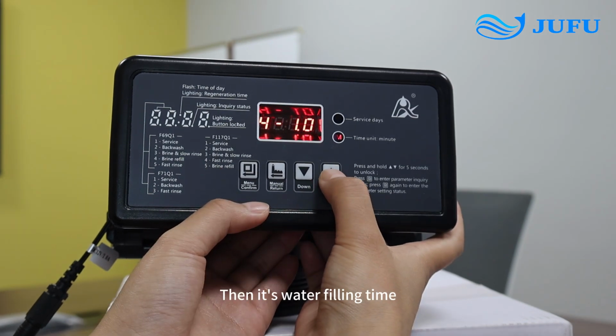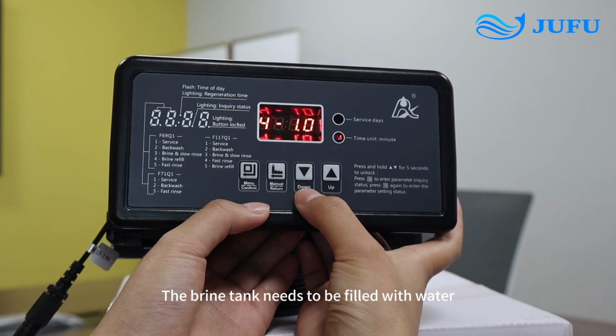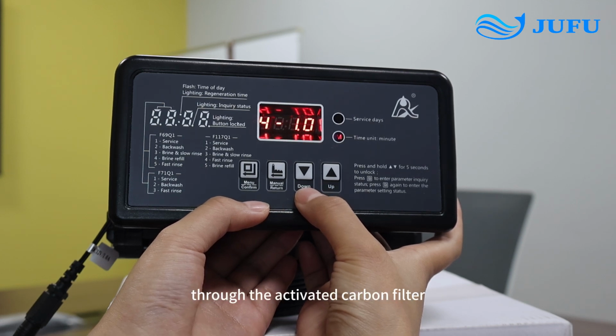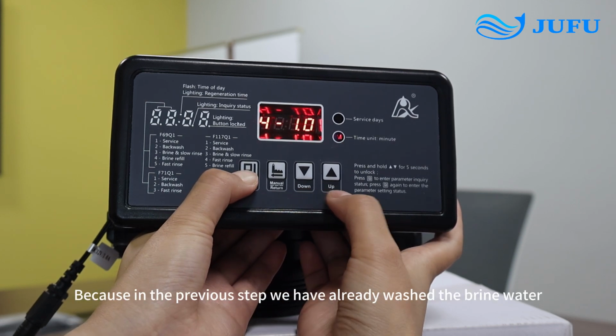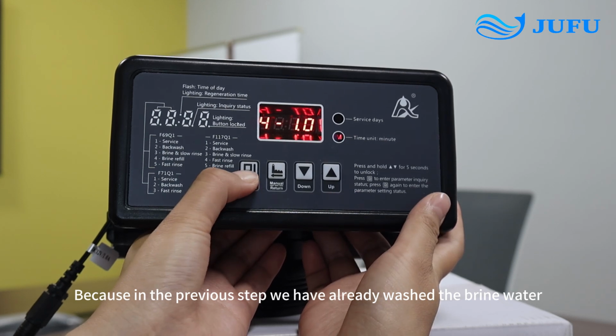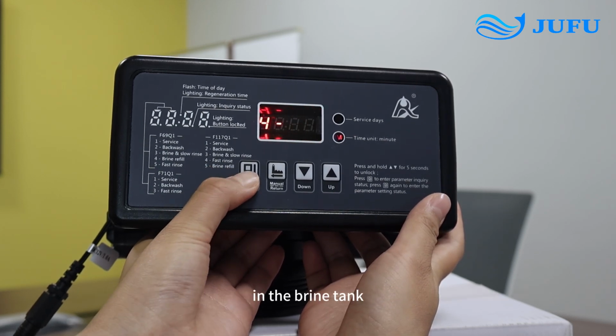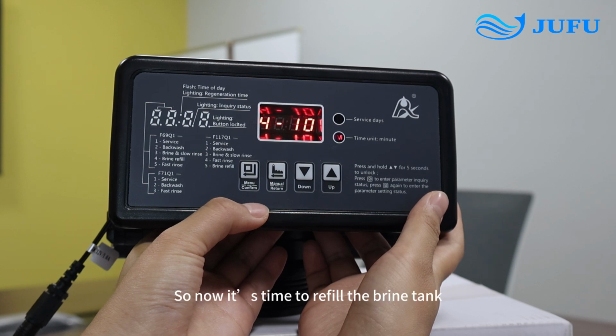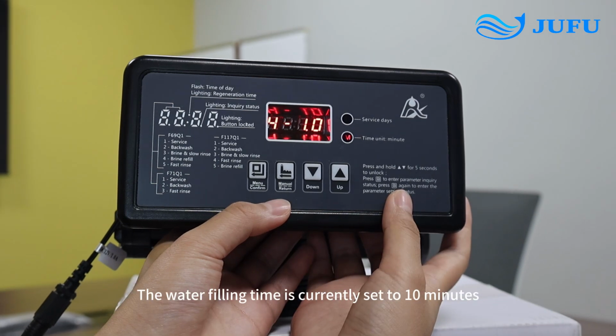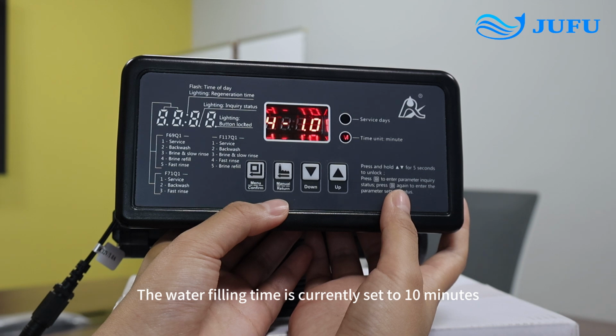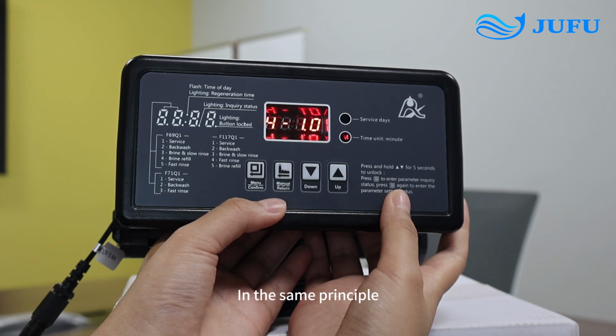Then is water filling time. The brine tank needs to be filled with water through the activated carbon filter. Because in the previous step, we have already washed the brine water in the brine tank, so now it's time to refill the brine tank. The water filling time is currently set to 10 minutes.